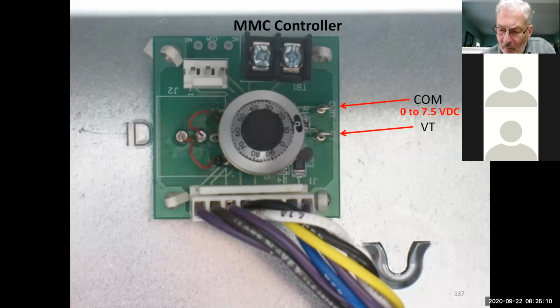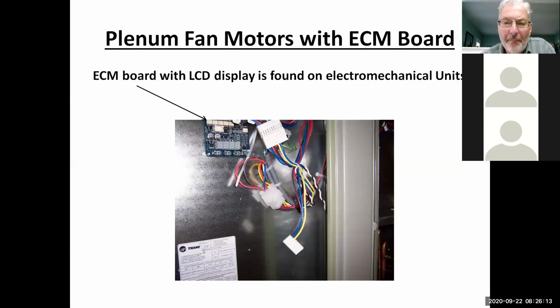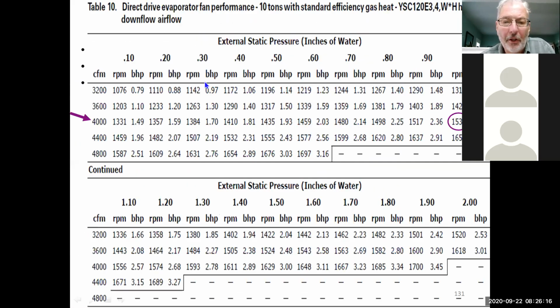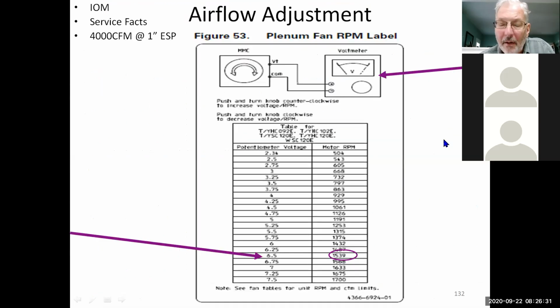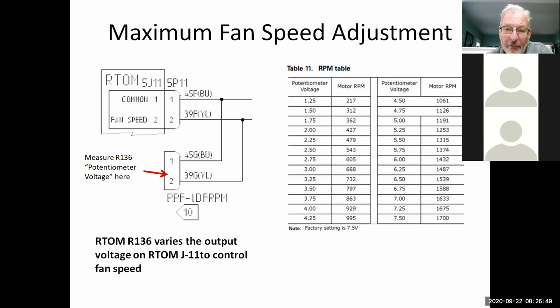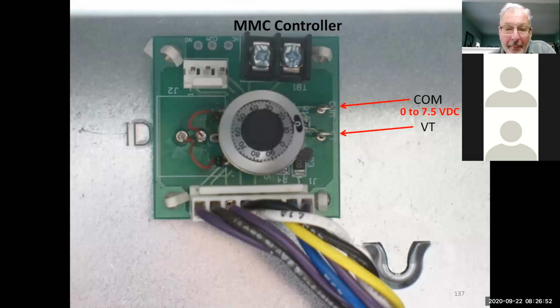So what I want to jump back to, though, is the nice thing with this is you can play with this a little bit. So say I want to dehumidify, I want to get to 3,600 at an inch of static. Well, I can run my blower at 1423. Or if I'm out west and I want more air, 1654. I can make that adjustment right here, and at 1432 I'm at 6 volts, and at 1633 I'm at 7 volts. So I've got some adjustment there. I can play with that. And it makes it a lot easier in the field to do some setup or some air balance. But that's the basic setup on the EBM motors.